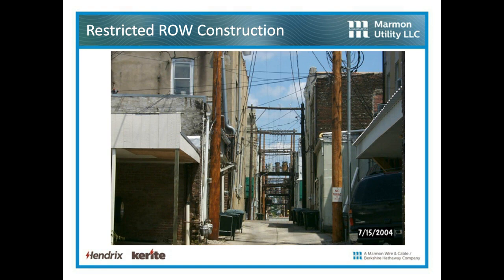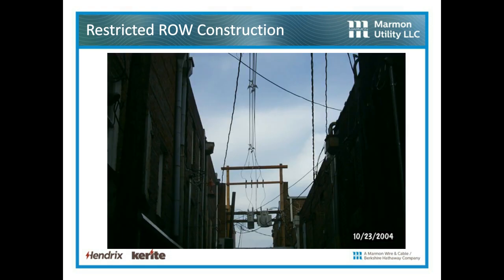Again, I can go underground, but that's expensive. There's all kinds of utilities down there. I can go over the roof with bare wire, 14 feet above the roof, but that creates a safety hazard. Or I can simply go with spacer cable. And that's what it looks like.